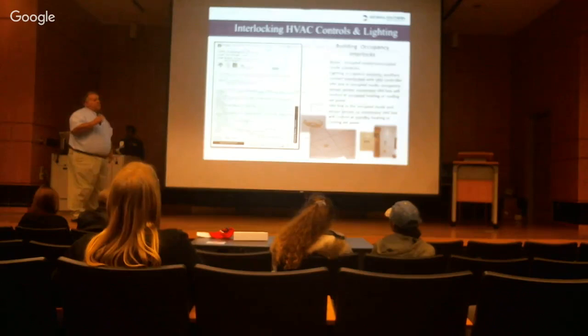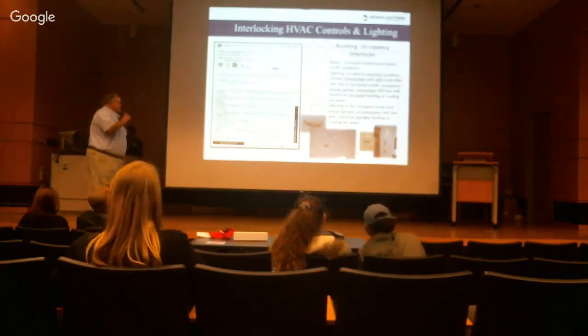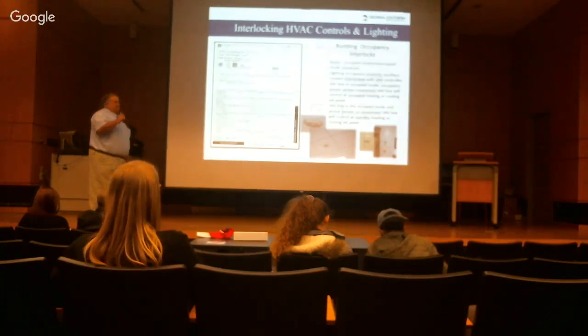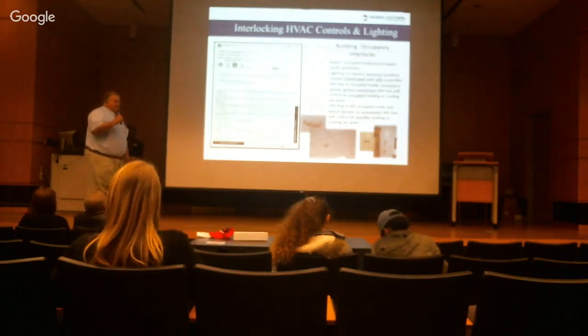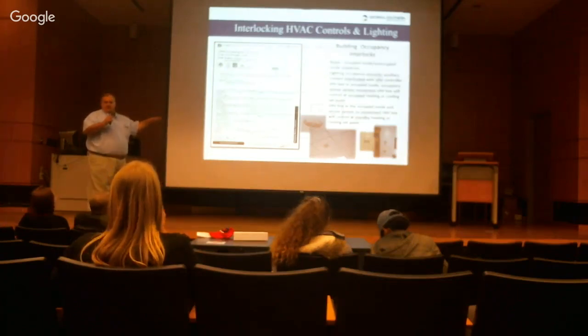This next one is a unique feature — I was actually talking to a vendor about it the other day. We put occupancy sensors in buildings, and in our scheme, we interlock those lighting occupancy sensors with VAV boxes in the space. So when the lights go out over a period across 3 or 4 rooms, the VAV box controlling that area throttles down and resets. We only move it about 2 to 3 degrees.